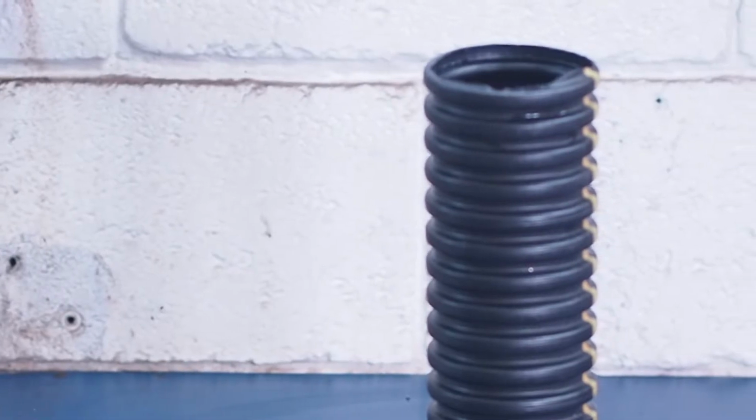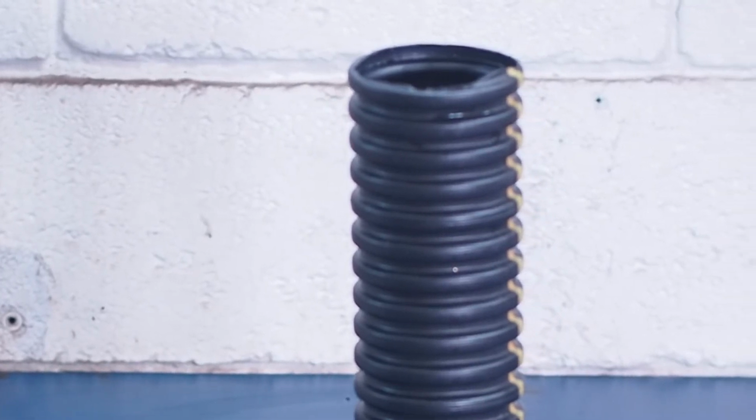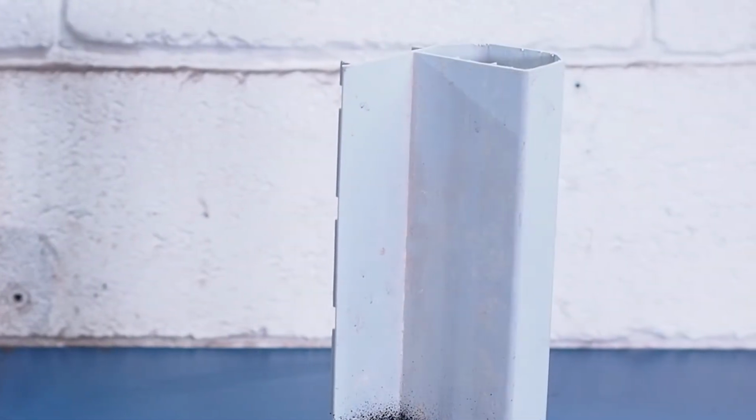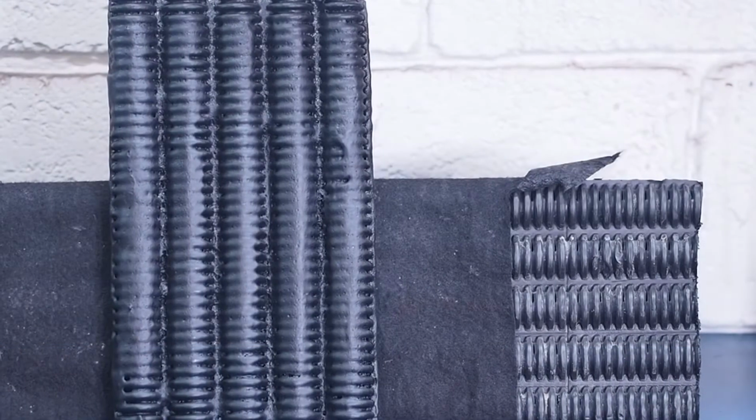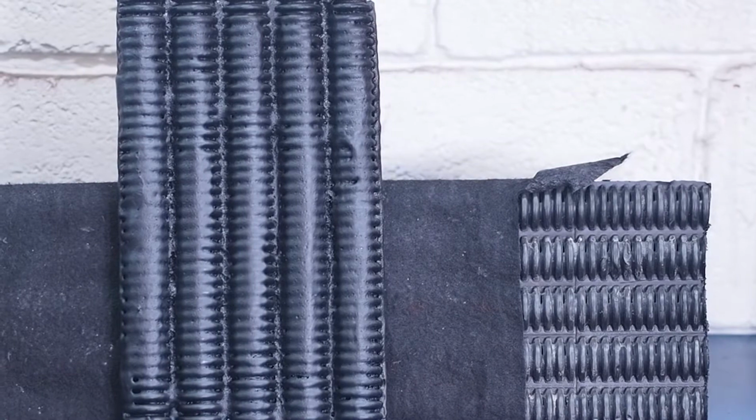For the purpose of retrofit subsoil drainage, commonly referred to as basement waterproofing, the Minnesota Uniform Plumbing Code specifies drainage conduit with a minimum 3-inch diameter.